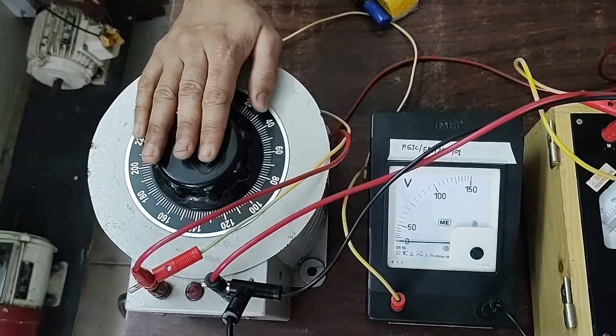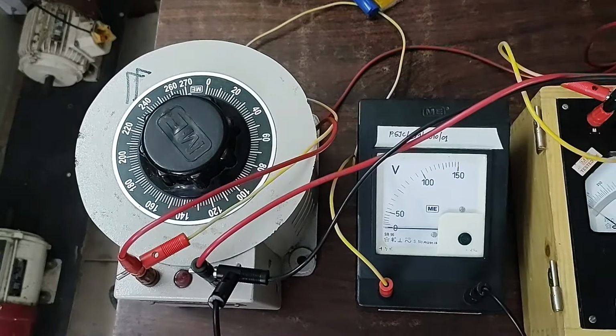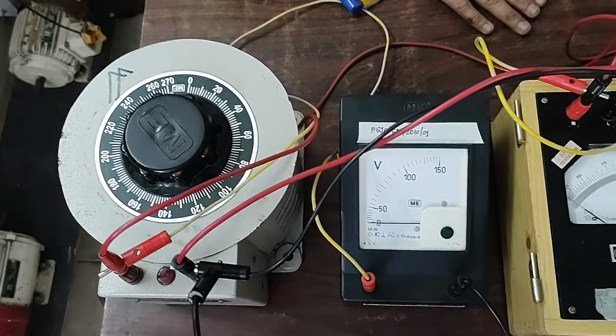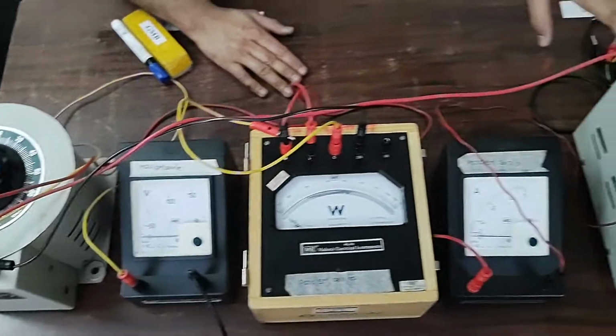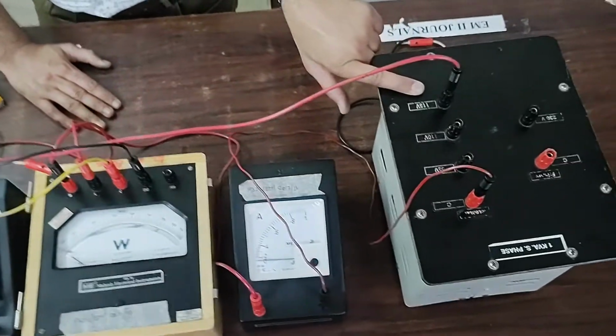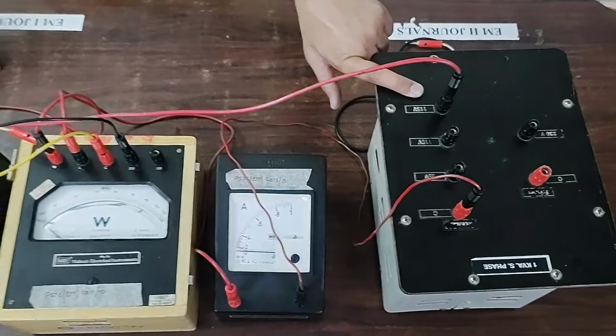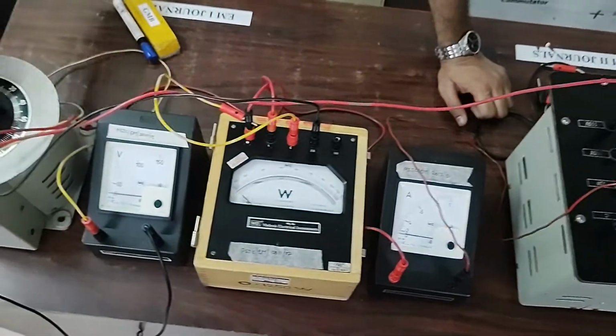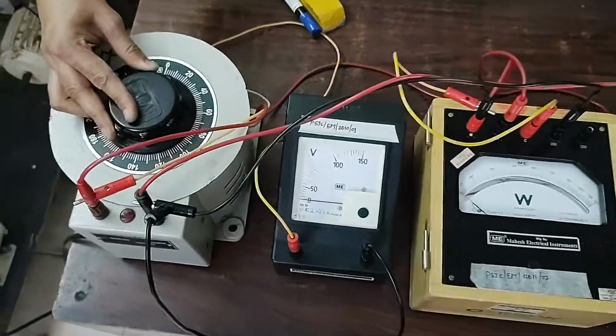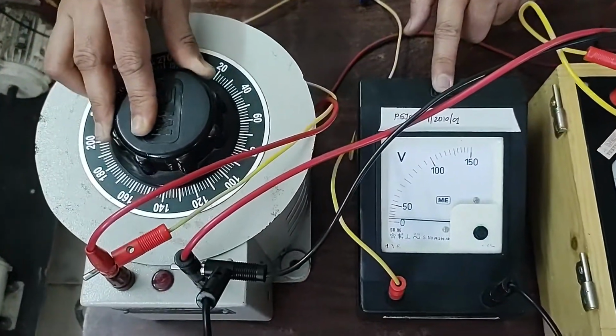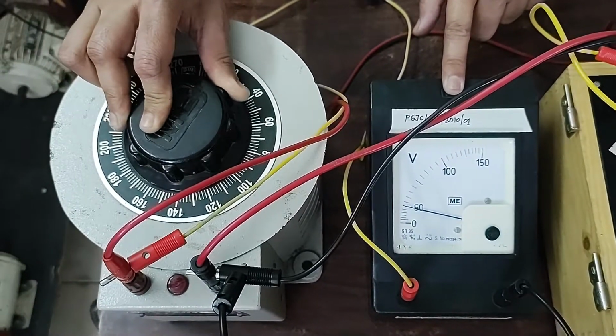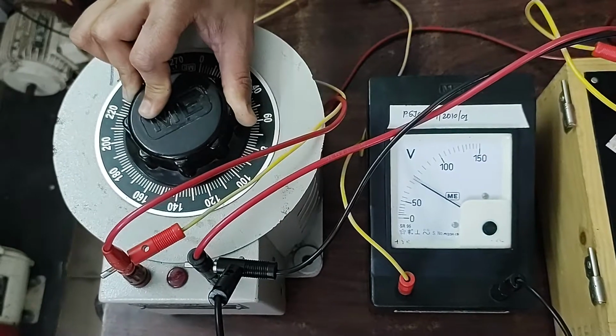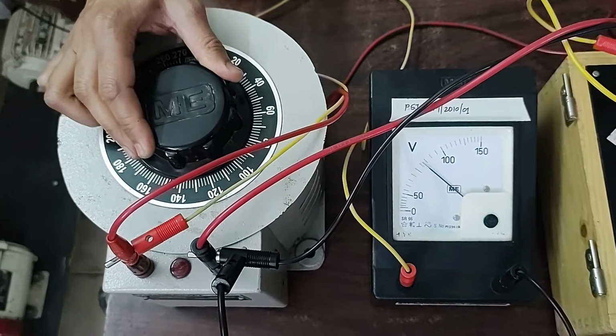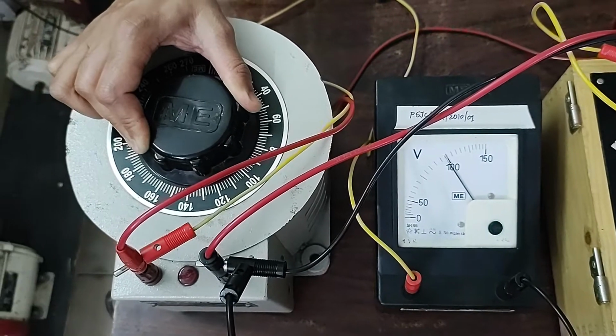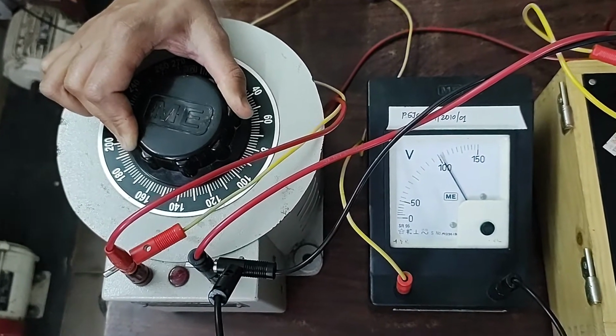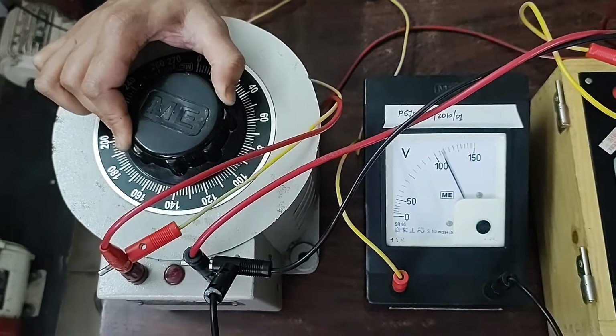Then with the help of the auto transformer, we have to apply rated voltage across the primary winding, which we are using as the 115 volt side. So across the primary we have to apply 115 volt with the help of the auto transformer. We will vary the knob of the auto transformer and keep a note of the deflection of the voltmeter. We have to increase it in a slow manner, and bring the primary voltage to 115.